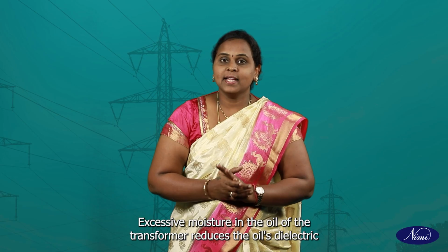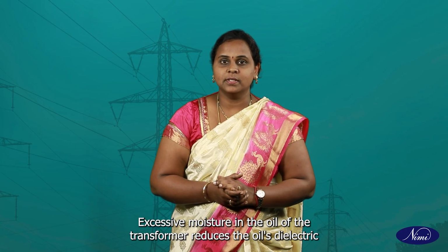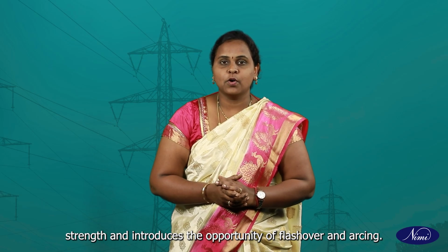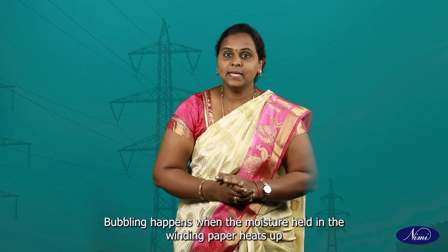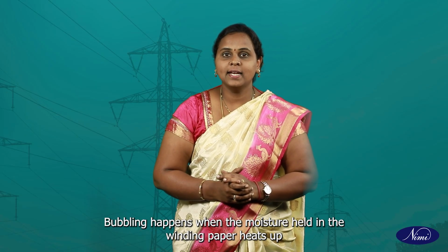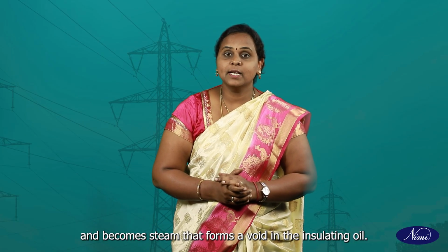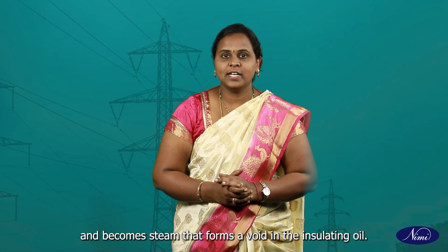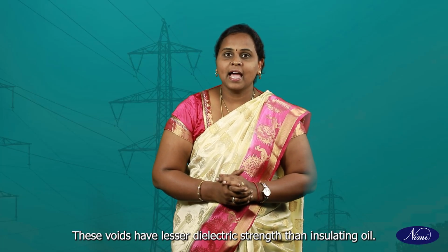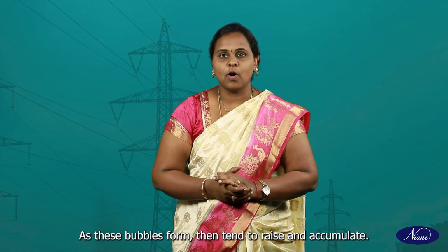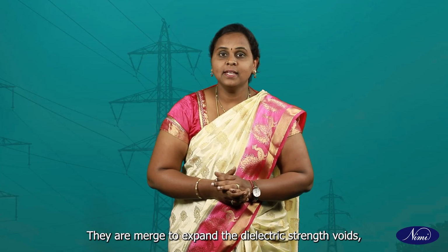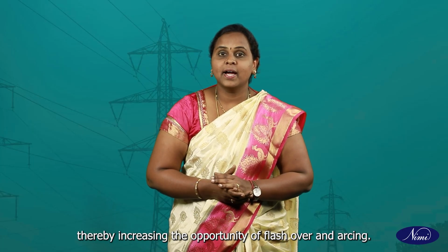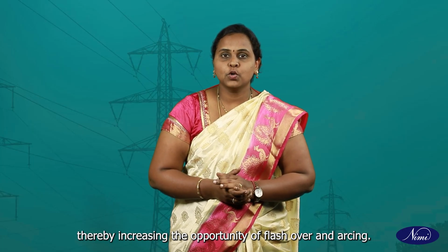Effect of moisture. Excessive moisture in the oil of the transformer reduces the oil's dielectric strength and introduces the opportunity of flashover and arcing. Bubbling happens when the moisture held in the winding paper heats up and becomes steam that forms a void in the insulating oil. These voids have lesser dielectric strength than insulating oil. As these bubbles form, they tend to rise and accumulate. They merge to expand the low dielectric strength voids, thereby increasing the opportunity of flashover and arcing.